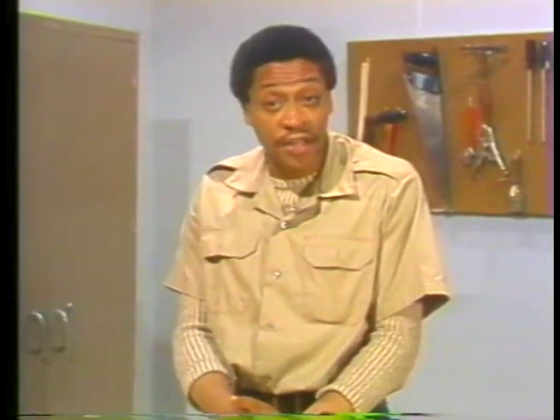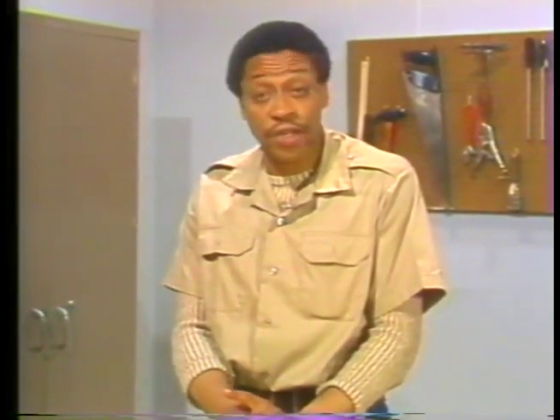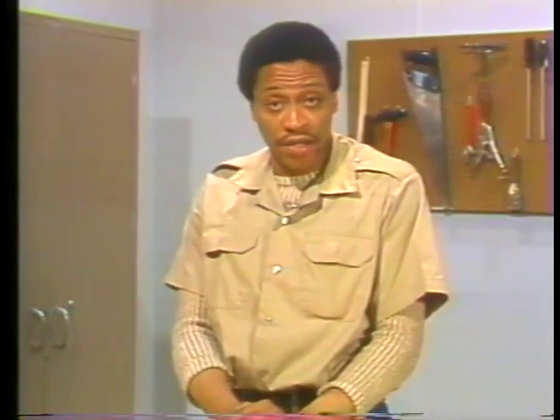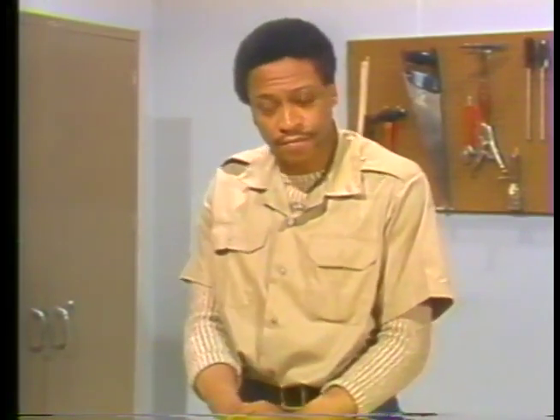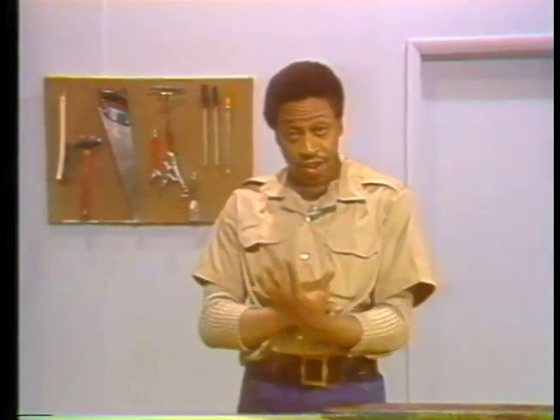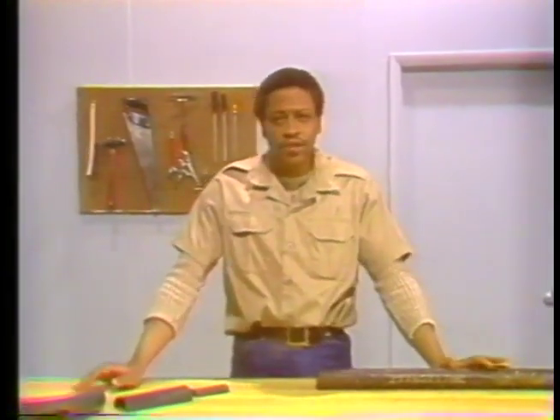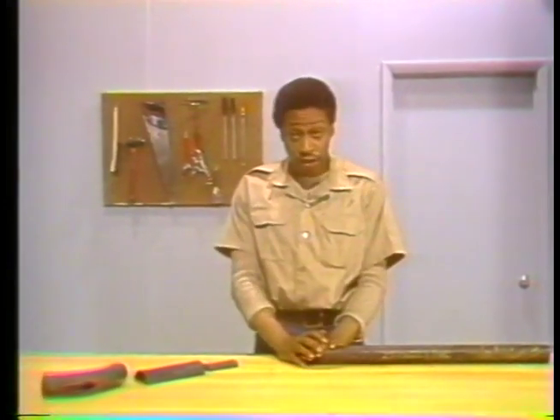Another cause of tube failure is a material defect — a weak spot in the tube metal that was there when the tube was manufactured. A tube with a material defect, like a thin spot in the wall, may fail as soon as it's put into service. Tubes should be inspected for material defects before installation, as a defective tube is much more likely to fail during normal boiler operation. We've now covered the five basic causes of tube failure: overheating, corrosion, erosion, mechanical stress, and material defects.